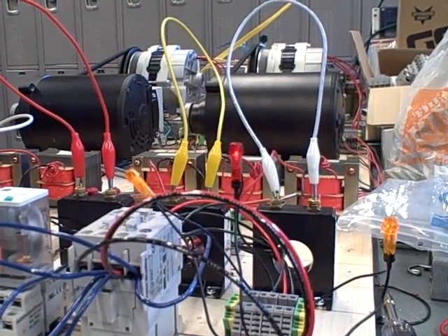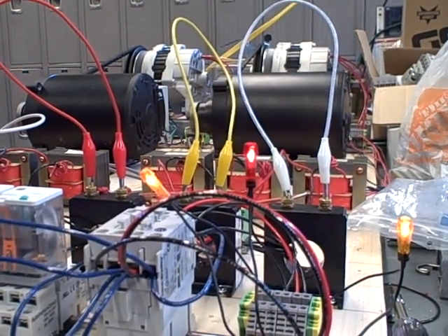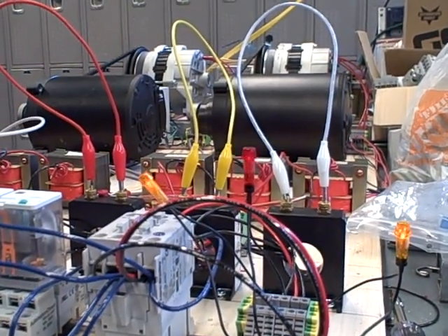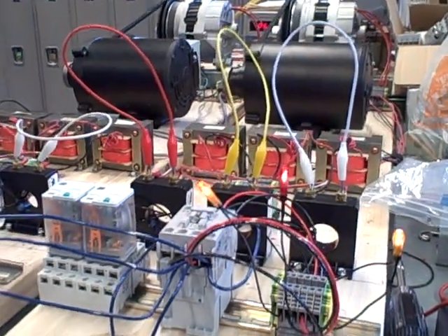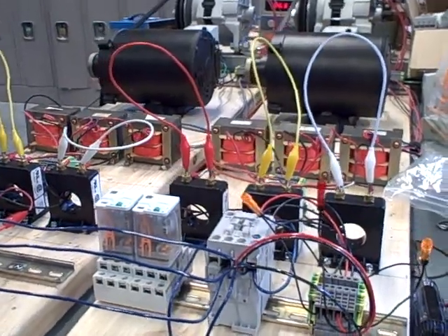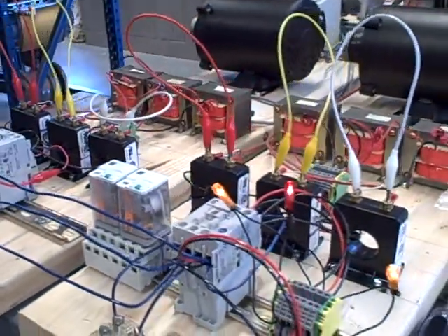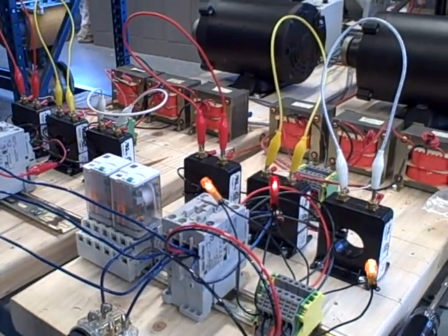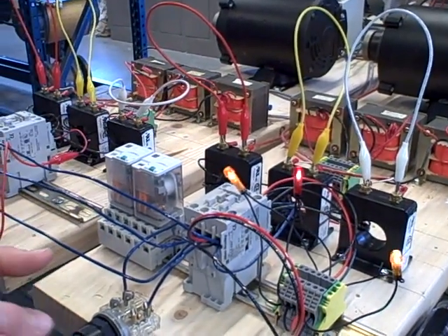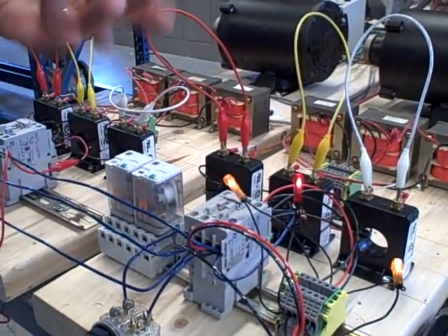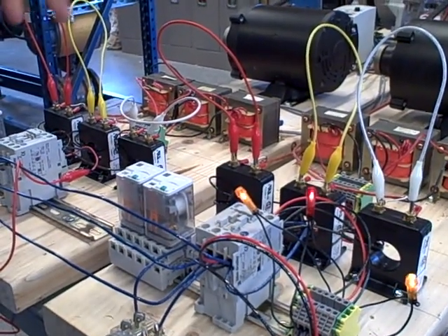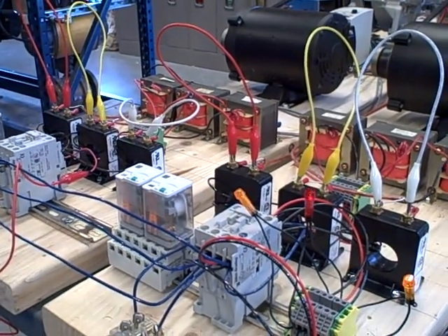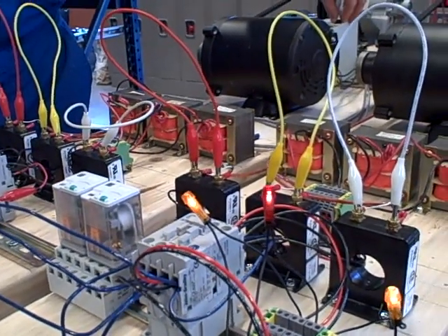So what we see here is a case where the sine waves in these two generators are very nearly the same frequency, and they're rolling in and out of phase with each other a little more than once a second or so. So imagine 60 Hz versus 59 Hz. That's about what we're looking at here. I'm going to increase the speed just a little bit more on the second generator until I get a slower blinking rate. Then I'm going to wait for the lights to go completely dark before I close my breaker. I don't want to close them when I have light because that would be closing a breaker across a substantial voltage difference, and that would be a transient event, a current that would shock the generators. I'm going to speed this generator up a little bit.